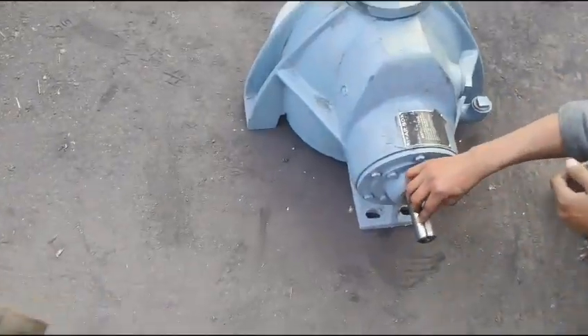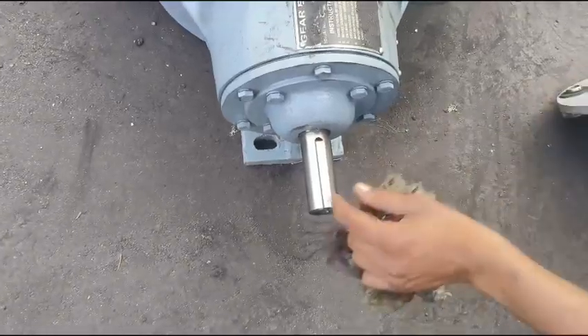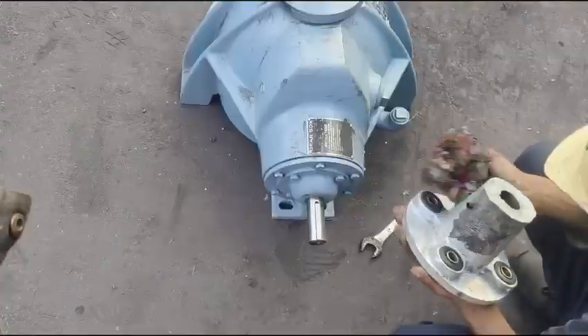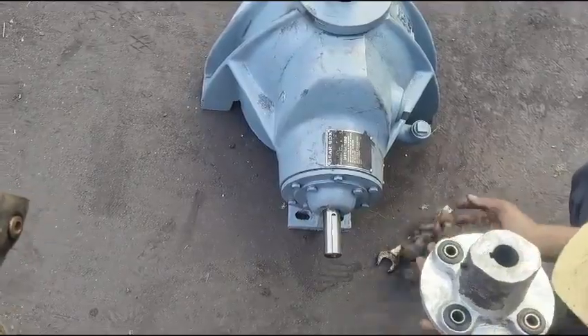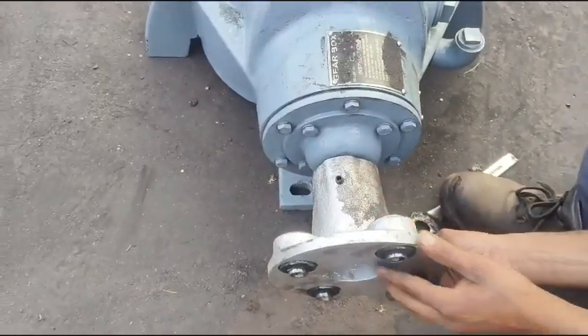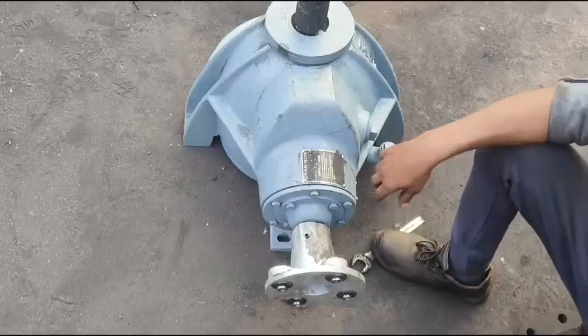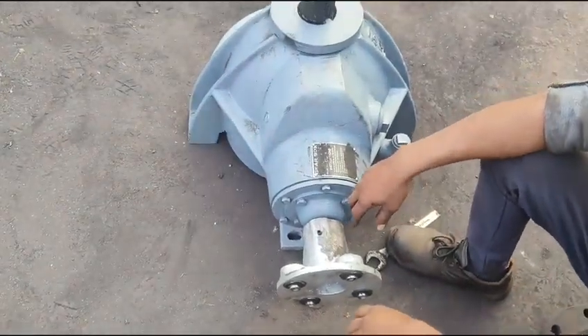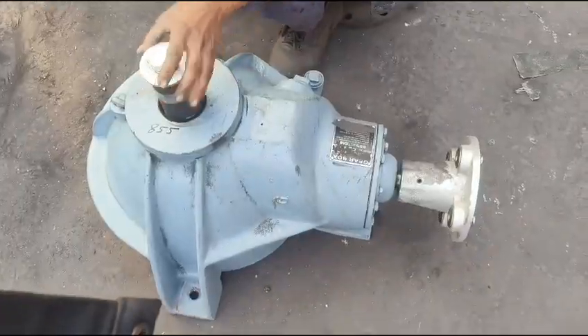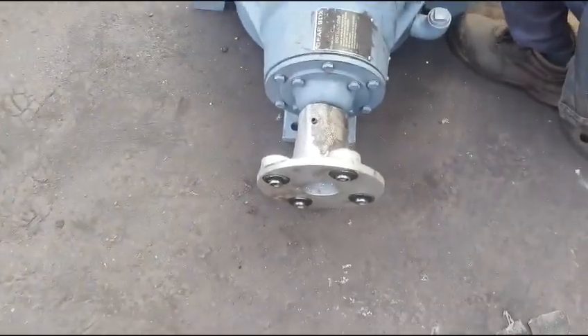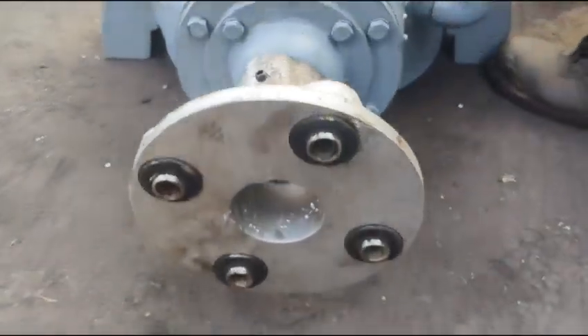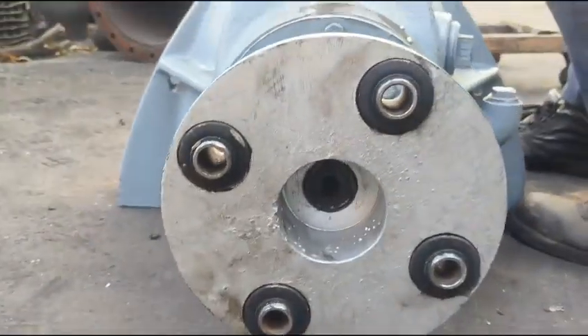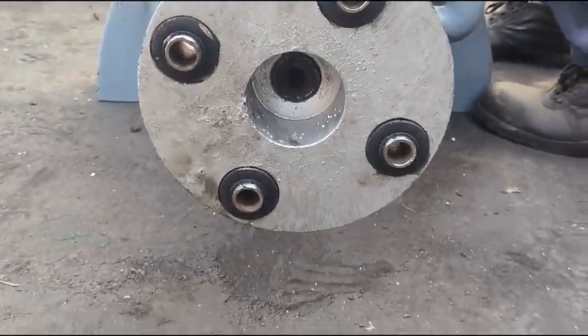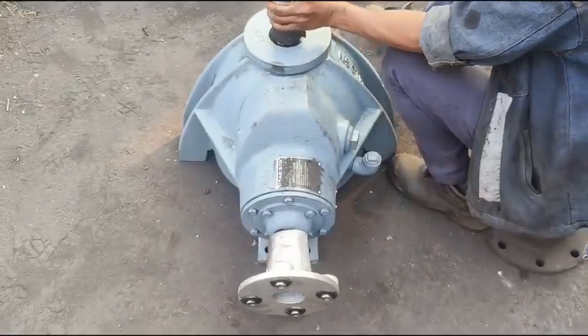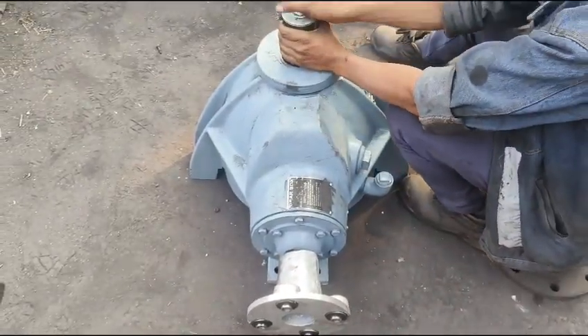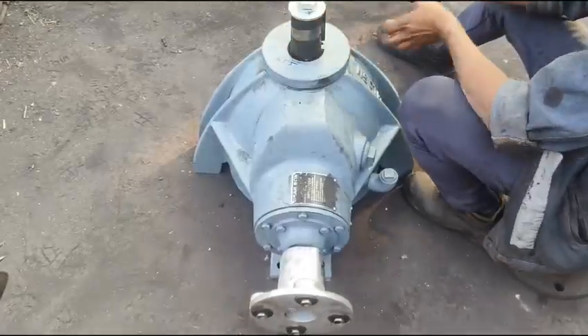First insert the key into the gearbox input shaft keyway. Now install the input shaft coupling on the gearbox shaft. Make sure the key is properly seated inside the keyway. Rotate the gearbox output shaft to confirm the gearbox is rotating freely.